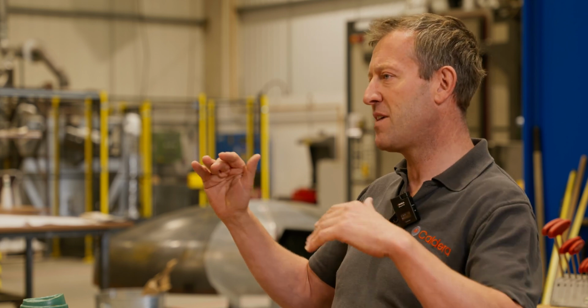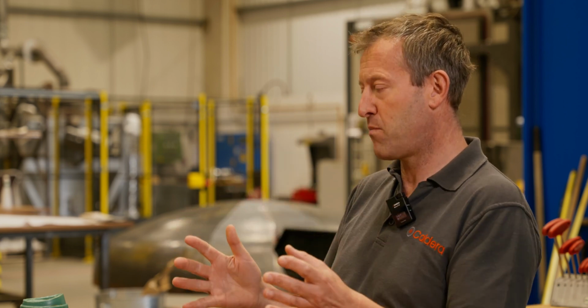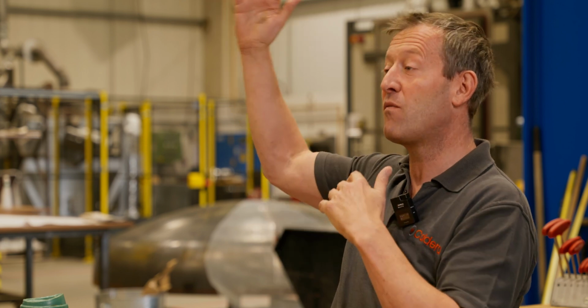So we can just use everything on site for electricity or heat. There was a second reason that we went there: industry tends to use heat at slightly hotter temperatures than homes, between 100 and 200 degrees Celsius, often in the form of steam. And even within the domestic space, there's a very clear pressure. We say under 100 degrees Celsius, use heat pumps. Above 100, it becomes harder and harder to deliver it with a heat pump.